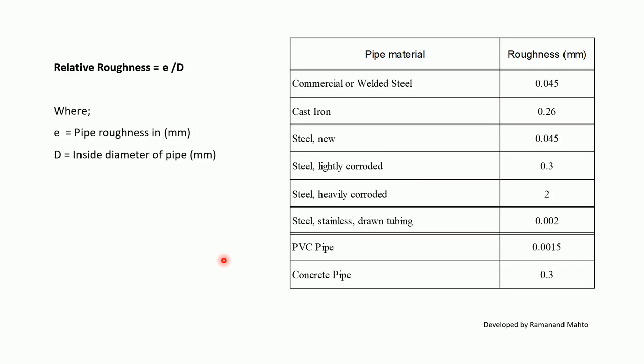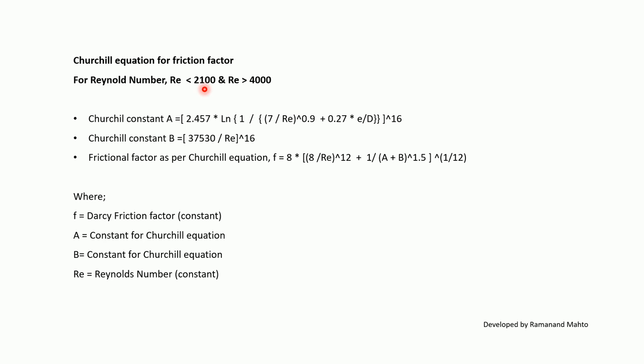Churchill equation for friction factor applies for Reynolds number less than 2100 and greater than 4000. Churchill constant A = (2.457 × ln(1 / ((7/Re)^0.9 + 0.27 × e/D)))^16. Constant B = (37530 / Re)^16. Friction factor: f = 8 × ((8/Re)^12 + 1/(A + B)^1.5)^(1/12), where f is Darcy friction factor, A and B are Churchill constants, and Re is Reynolds number.